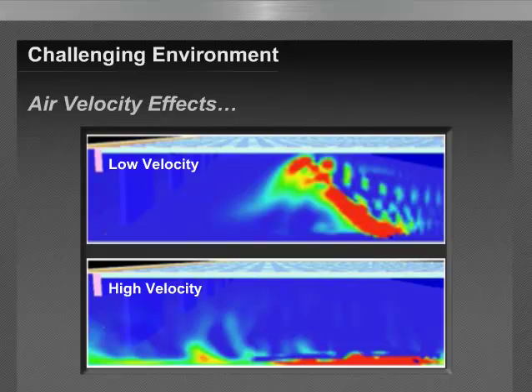So since the rate of smoke generation in a smoldering fire is relatively small and the airflow velocity in the room quite high, we look at the movement of smoke, which is dominated by that airflow in the mechanical systems. And then, as we mentioned earlier, the effects of smoke being cooled by the airflow has very little buoyancy to get it to the ceiling. This often prevents smoke from moving directly to the spot detectors that reside at ceilings where they perhaps would be located, causing smoke to dissipate more widely. So on certain cooling configurations, air velocities are also exceeding conventional detector-rated listings. So a variety of challenges when you think in terms of airflow patterns and airflow velocities.